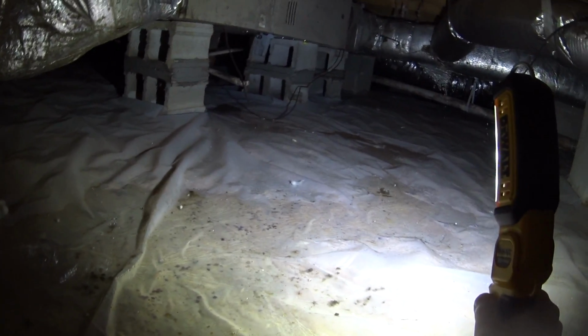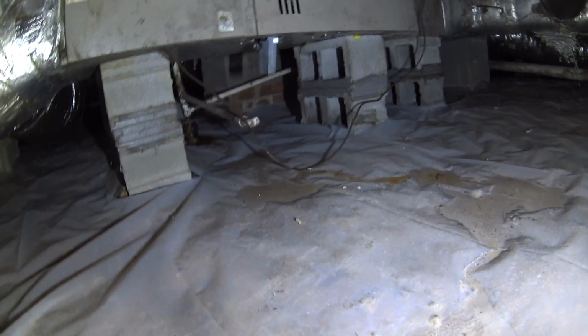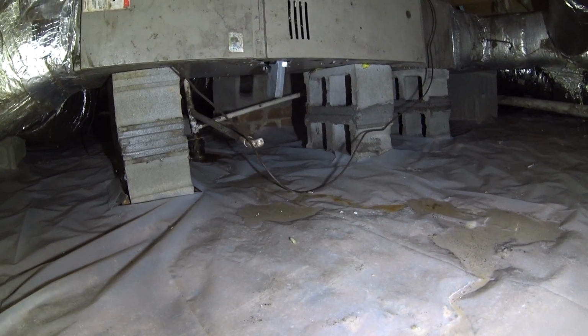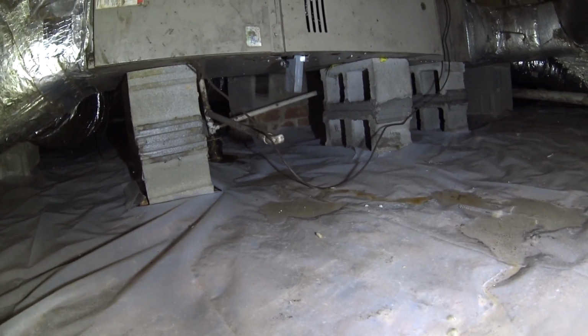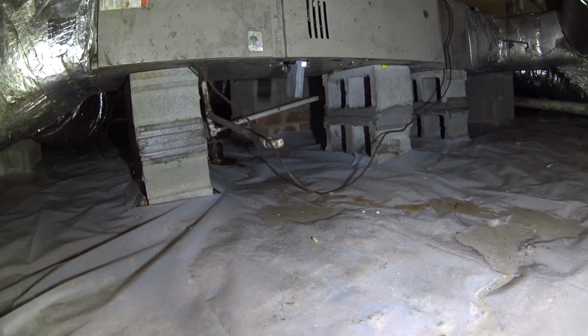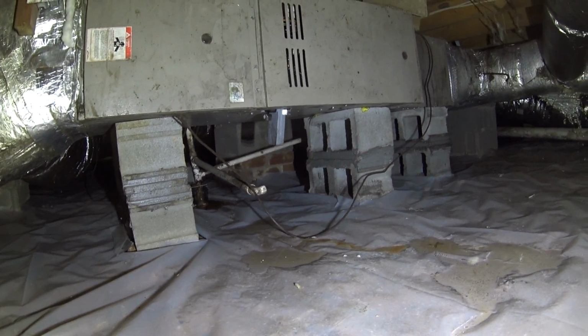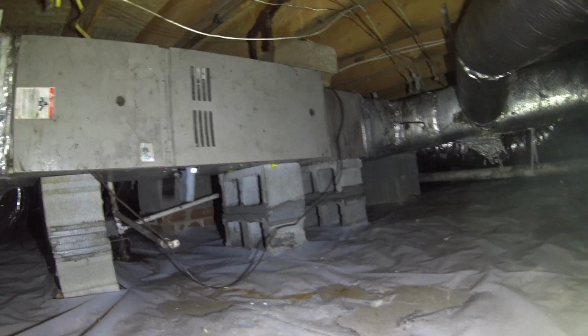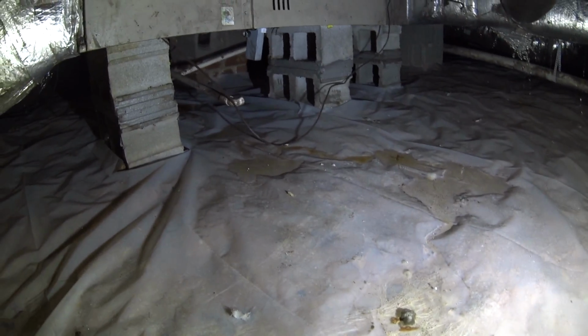Well, this is not the house that I thought it was, but it is a customer that I've been to before, though I haven't done a whole lot of work down here in the crawl space. What I'm seeing is some moisture, and it appears that it's probably due to the fact that the drain is disconnected, and it looks like maybe the condensate pump is not functioning properly. So we'll dig into the furnace a little bit before we go that far, see what it looks like before we go make a recommendation for a new condensate pump, possibly.